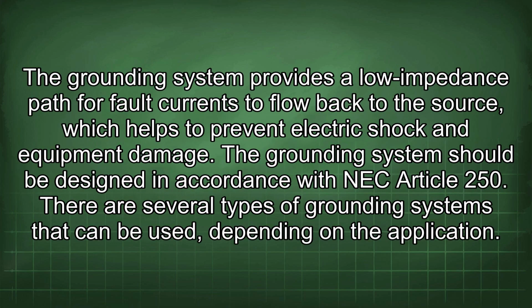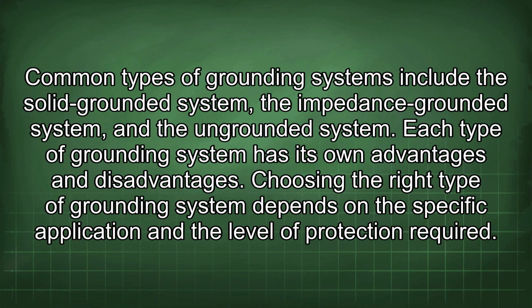The grounding system provides a low impedance path for fault currents to flow back to the source, which helps to prevent electric shock and equipment damage. The grounding system should be designed in accordance with NEC Article 250. There are several types of grounding systems that can be used, depending on the application. Common types of grounding systems include the solid grounded system, the impedance grounded system, and the ungrounded system. Each type of grounding system has its own advantages and disadvantages. Choosing the right type of grounding system depends on the specific application and the level of protection required.